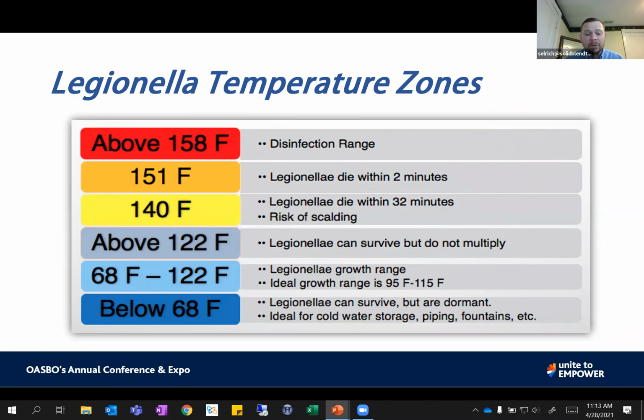As you can see, though, Legionella growth range ideal is 95 to 115. Typically, your incoming cold water is going to be 65 to 70 degrees from the city. We're going to put that into our domestic hot water system, and we're going to get that temperature up to 120 coming out of the fixtures. So we're really in that ideal range. If you notice, though, at above 122, Legionella can survive, but does not tend to multiply as well or thrive and reproduce. So what we like to work with our clients and partners on is you can maintain your hot water tanks and temperatures in those tanks above 122 and still use mixing valves and other engineering devices to meet your scald requirements at the fixture.